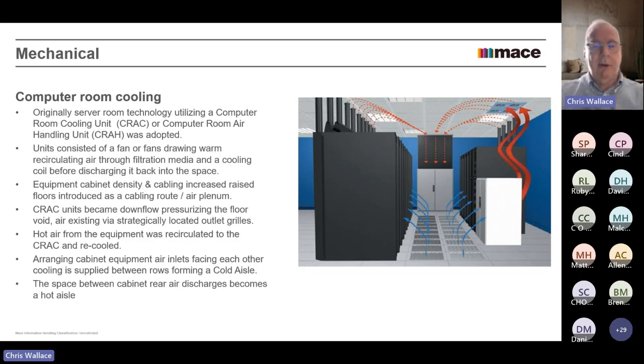And they thought, why don't we... Believe it or not, it seems so logical now, but I can remember when people didn't do it. Why don't we spin the cabinets around so we have all the inlets facing each other and all the outlets facing each other? What you then have is roughly what's on this diagram here, where the inlets are all fed with cold air and all the outlets discharge into a common hot air space. This was termed hot and cold aisles, the aisle being the walkway between the cabinets.